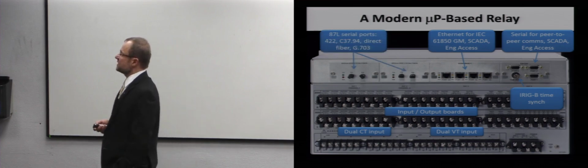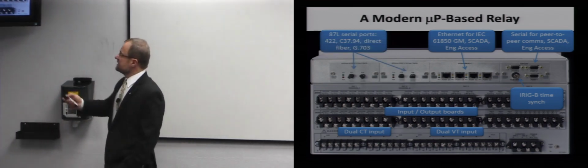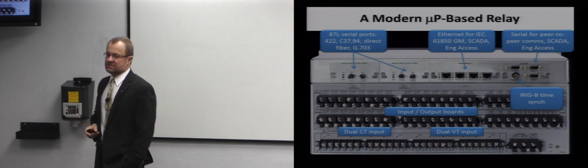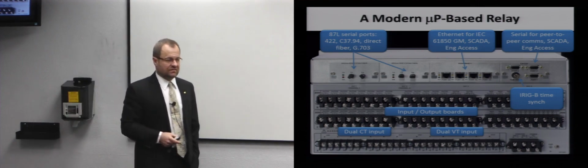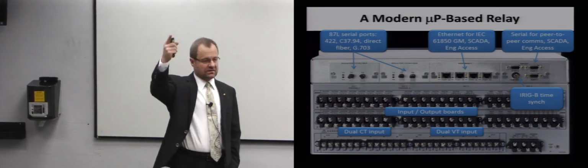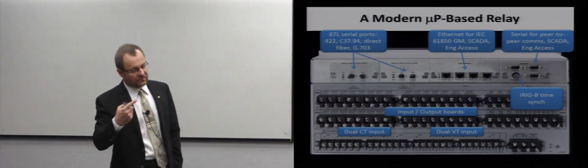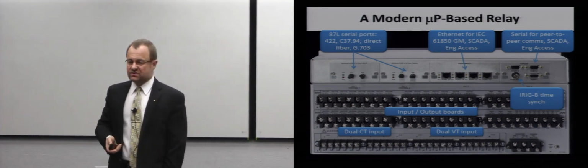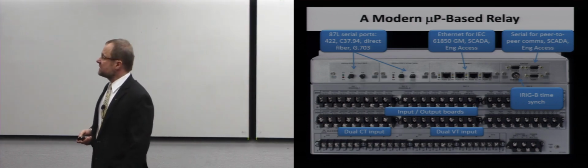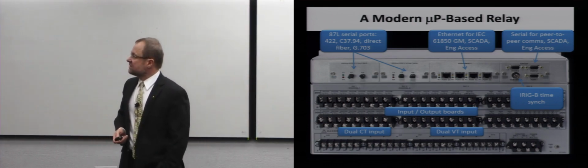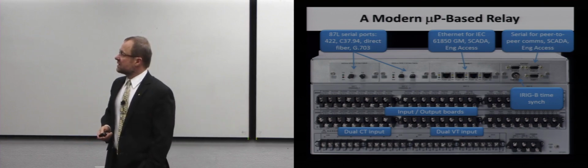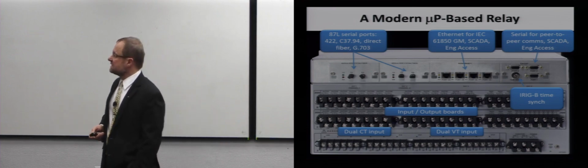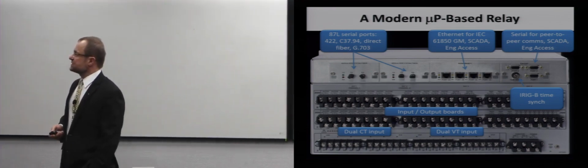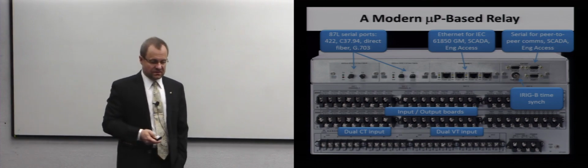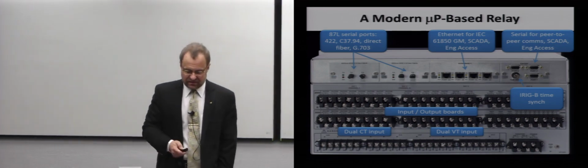You may have fiber-based communications to other relays. For example, this relay is a line current differential relay. It talks with another relay like that at the other end of the line, sending current signals back and forth. So this could be done, and is done, via fiber. Either you go directly to the other end or you go to a communications network such as SONET using time division multiplexing. There is a standard connection between relays and multiplexers. So this is the back of the relay.